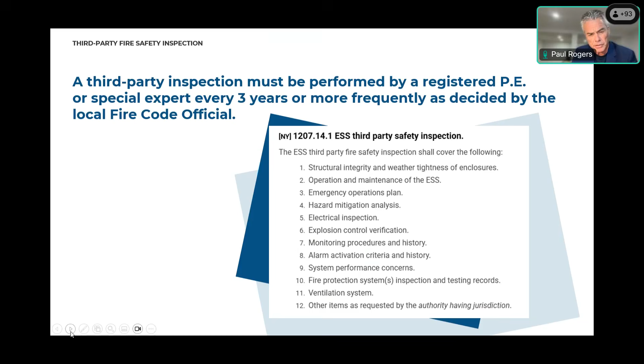A third-party inspection must be performed by a registered, licensed professional engineer from the state of New York, or a special expert, every 3 years or more frequently as decided by the local fire official—so it gives some latitude. This is in section 1207.14.1, and all of the things needed for the inspection are appropriately listed there.